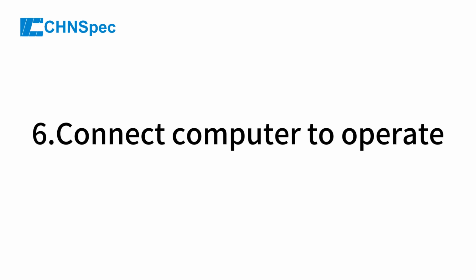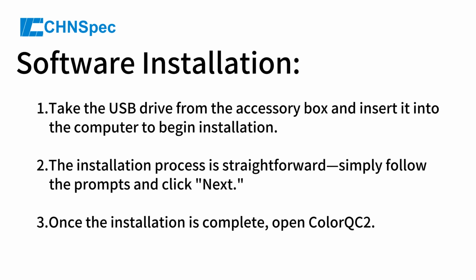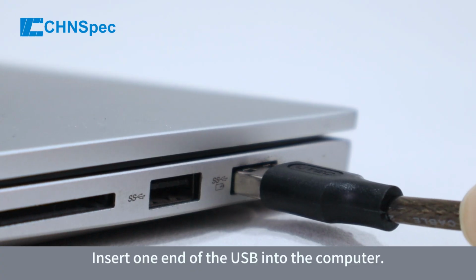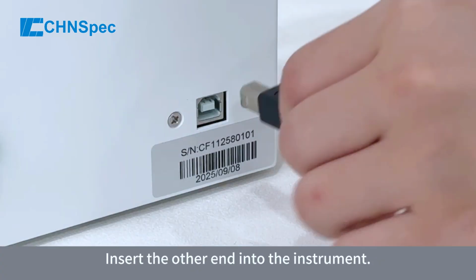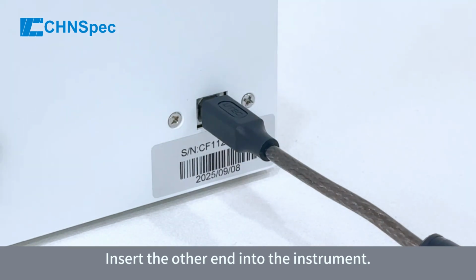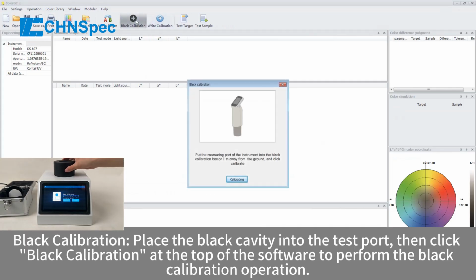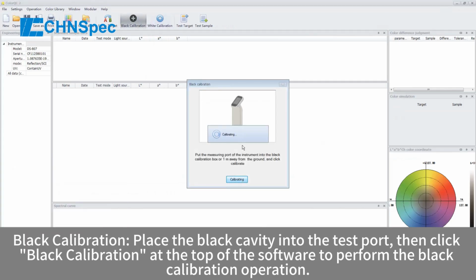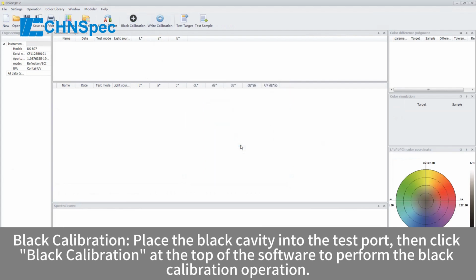6. Connect computer to operate. Insert one end of the USB into the computer. Insert the other end into the instrument. Black calibration. Place the black cavity into the test port. Then click Black calibration at the top of the software to perform the black calibration operation.